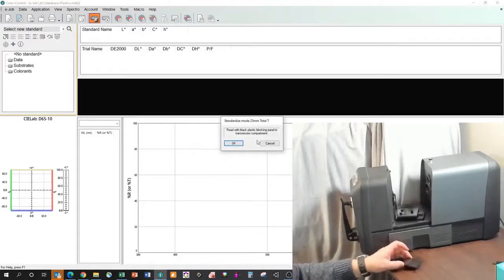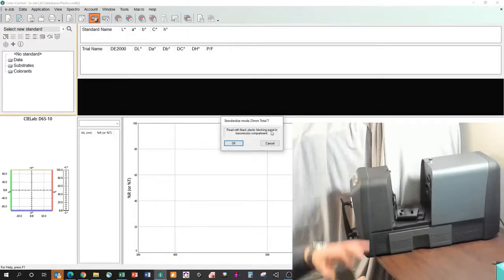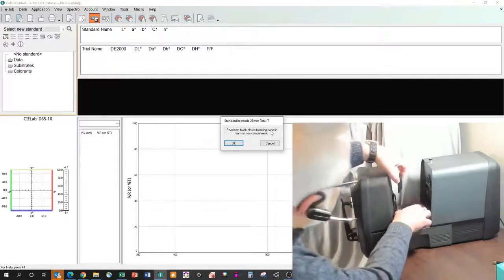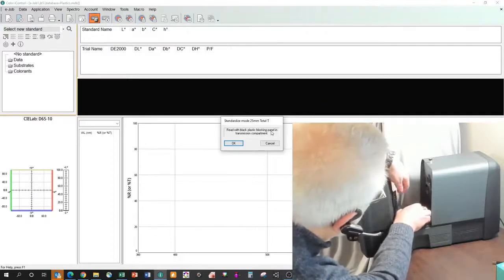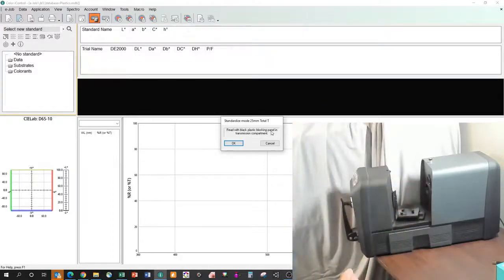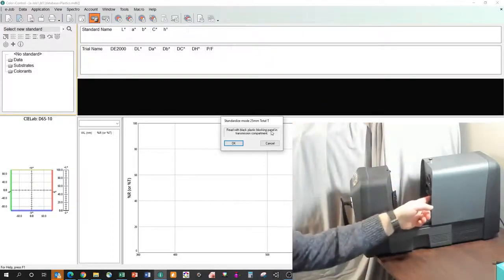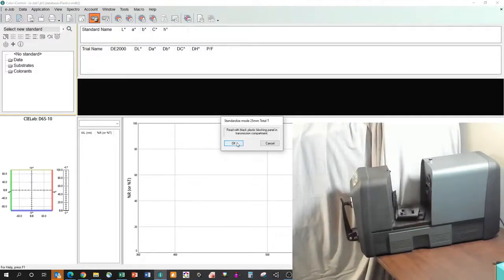And now the software says to read with a black plastic blocking panel in. And what this is going to do, I lock it in just like I was going to measure a sample, let the clamp hold it in place. It's going to prevent any light from passing through so that we can see what a zero calibration looks like. We go ahead and take that measurement, that calibration, and our calibration is completed. So now we're ready to take measurements.